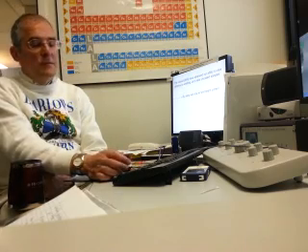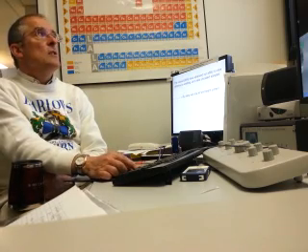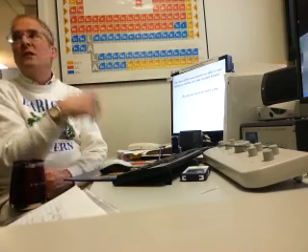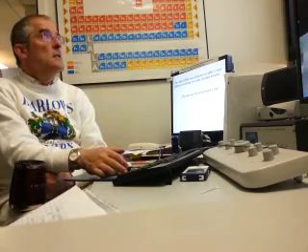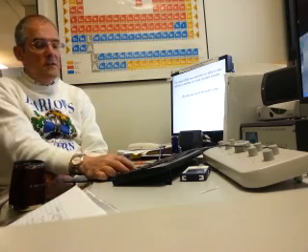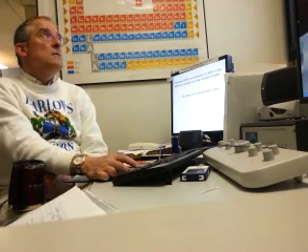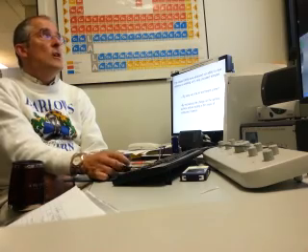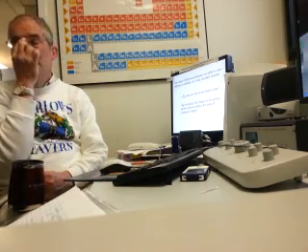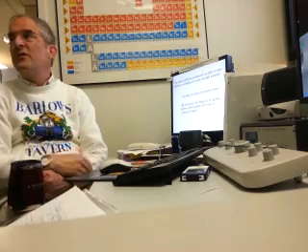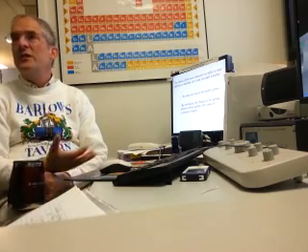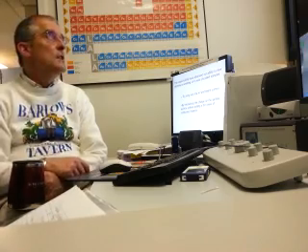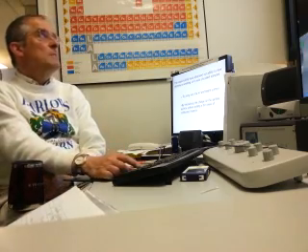All right, so viewing uncoated samples, we can lower the KV to reduce the amount of current hitting it so you don't get the buildup of charge on it. This would be a sample that's not conductive. You can also neutralize the charge on the sample surface. One way to deal with the charge on the surface is to coat it. If you're dealing with museum samples, they frown on you putting a coating on a rare specimen.